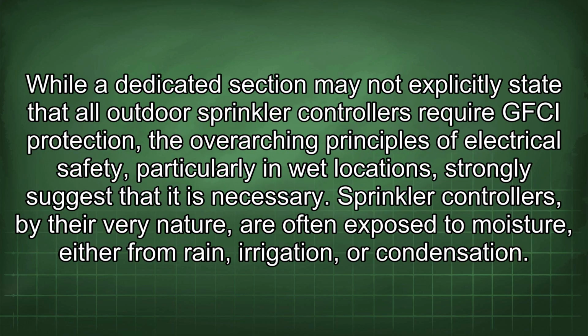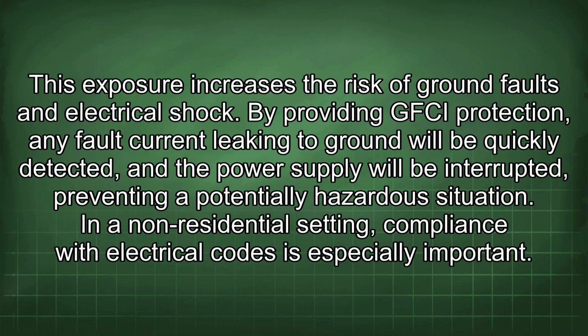While a dedicated section may not explicitly state that all outdoor sprinkler controllers require GFCI protection, the overarching principles of electrical safety, particularly in wet locations, strongly suggest that it is necessary. Sprinkler controllers, by their very nature, are often exposed to moisture, either from rain, irrigation, or condensation. This exposure increases the risk of ground faults and electrical shock. By providing GFCI protection, any fault current leaking to ground will be quickly detected, and the power supply will be interrupted, preventing a potentially hazardous situation.